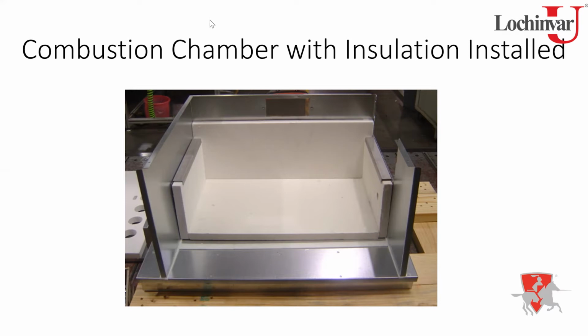Whenever you're looking in here, you're going to see some discoloration sometimes, a couple of scratches, a couple of nicks here and there. I'm okay with that. But if the thing's falling apart, with big cracks, that's what I'm worried about. If you see that, don't put the unit into operation until that issue has been resolved and those pieces have been replaced.